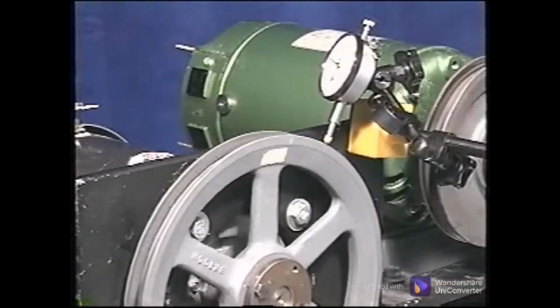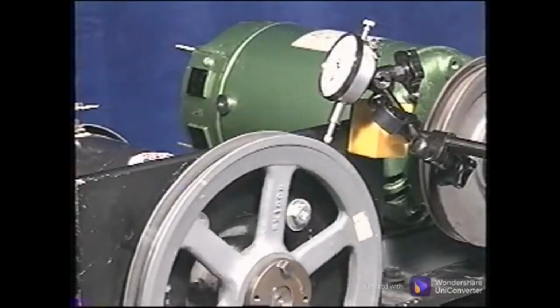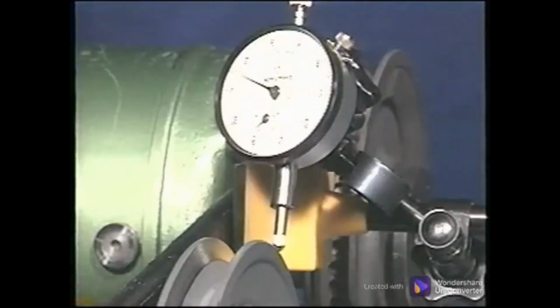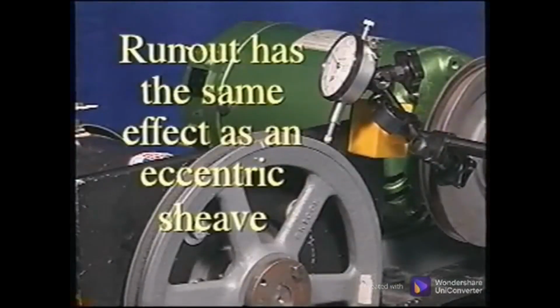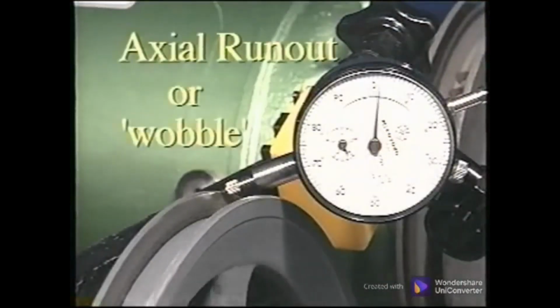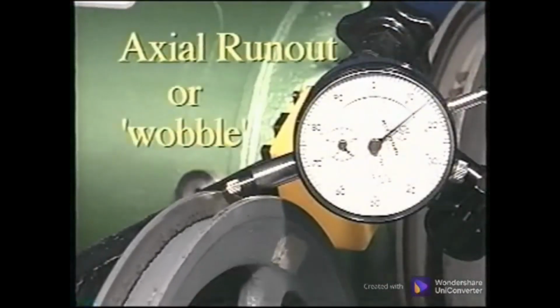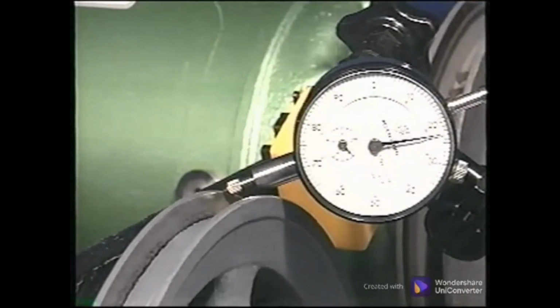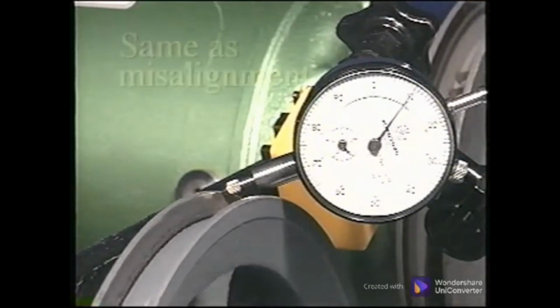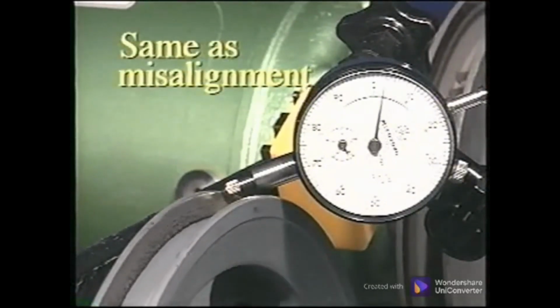Machining tolerances for runout on the sheave diameter can be up to 10 thousandths of an inch. Coupled with belt discrepancies, the total runout could be as high as 30 thousandths. This runout has the same effect as an eccentric sheave. Axial runout or wobble generates axial motion in the same way that misalignment does, because the belts ride up in the groove and pull on the shaft. Wobble has the same spectral characteristics as sheave misalignment.